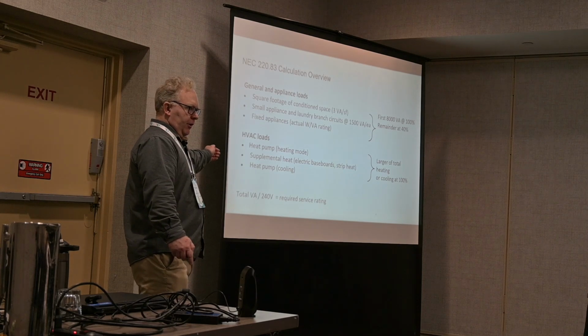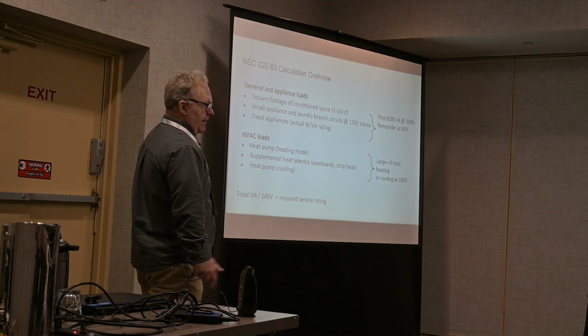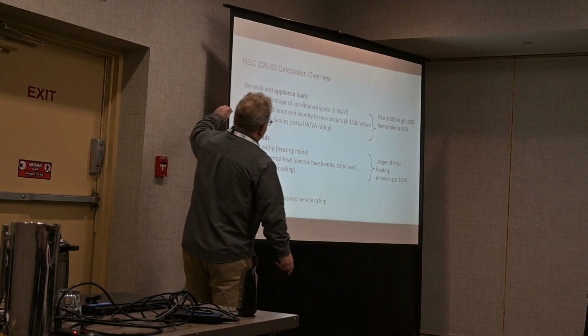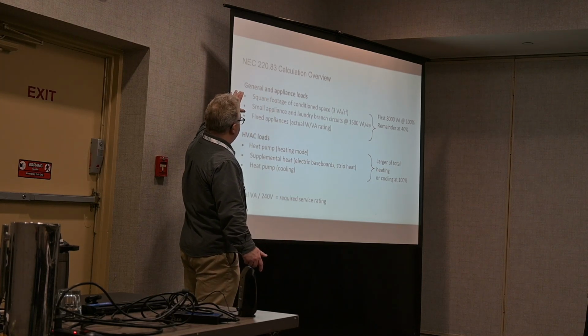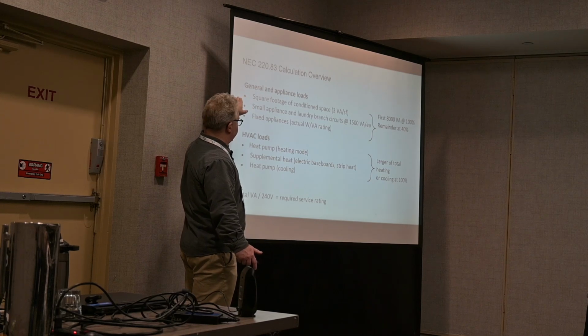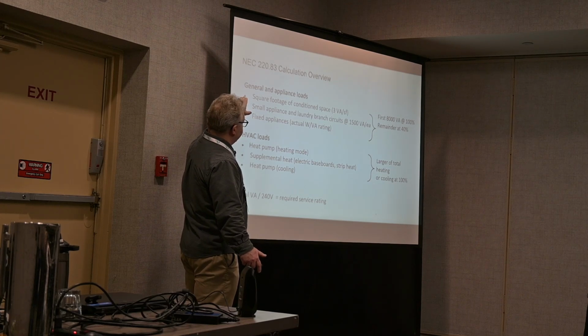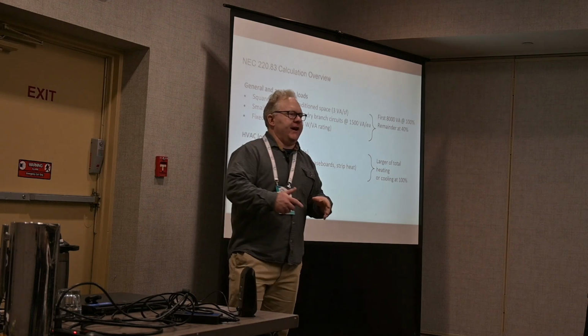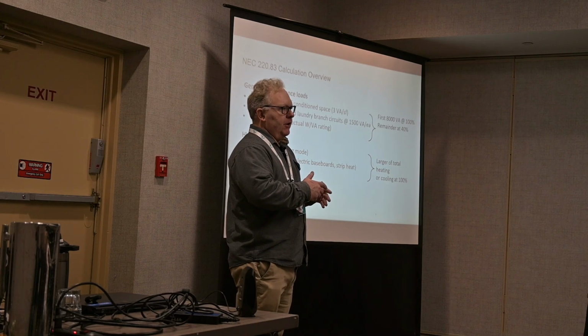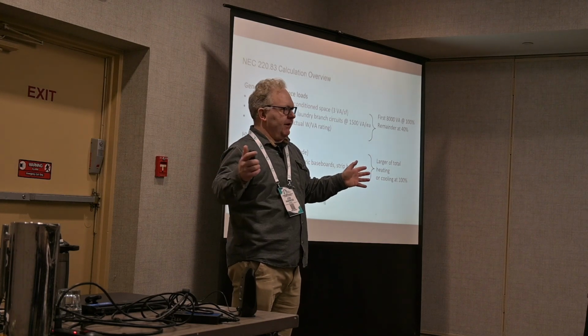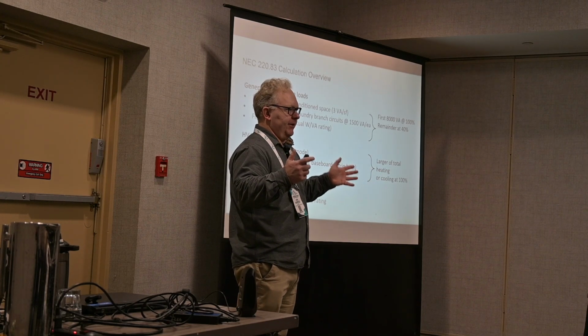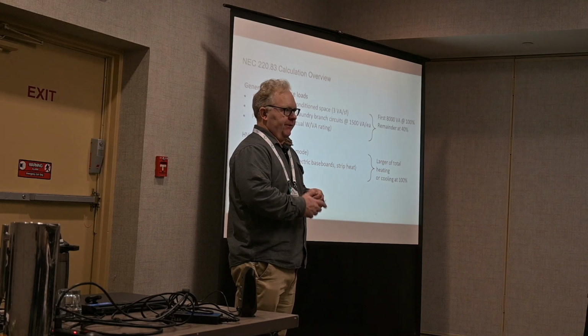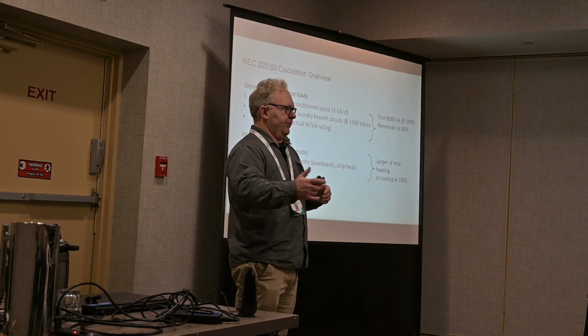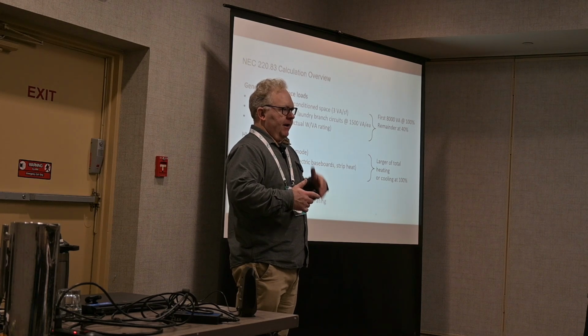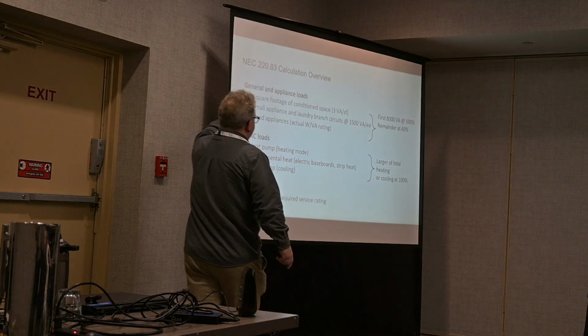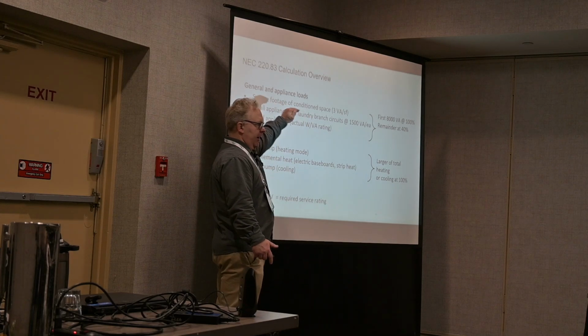So just to give you a quick overview of the big view of this calculation, it's broken into two parts. One is the general and appliance loads. And what this calculation recognizes is that no one uses all the electrical appliances in their house at the same time. Refrigerators cycle on and off. Ranges are used half an hour here and there. Lights are turned on and off. So we don't need to add up every single load at 100%.